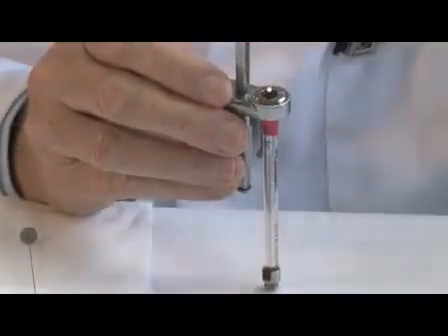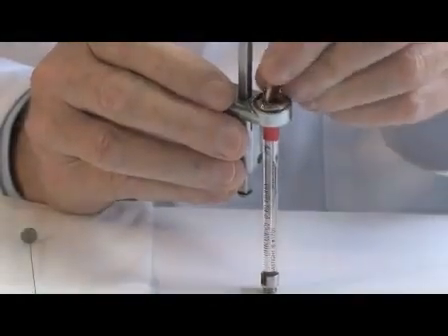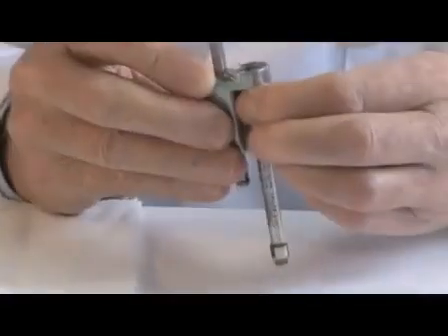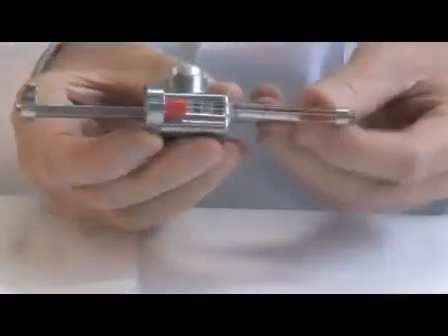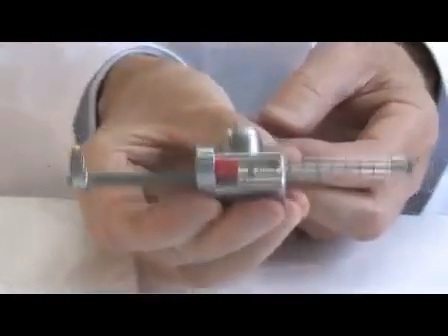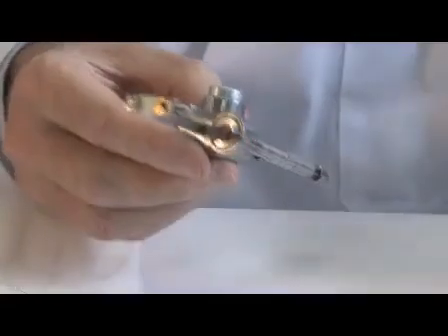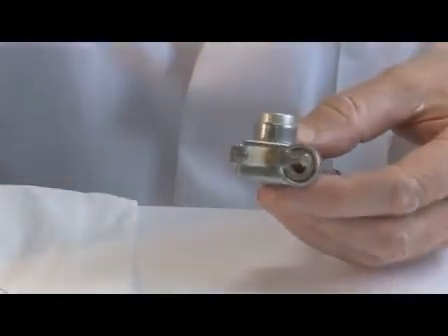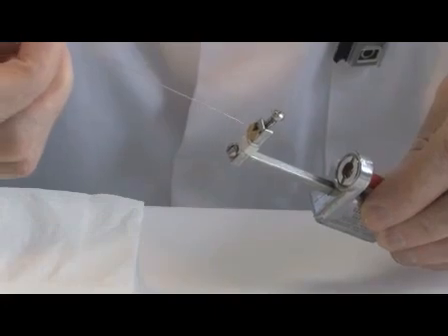Care should be taken to ensure the syringe is properly centered in the holding ring and that the barrel is aligned parallel to the ratchet arm. Both can be judged by eye. These two requirements are important because if the plunger does not run free and true, pressure will build up in the source syringe during loading and leakage can occur.